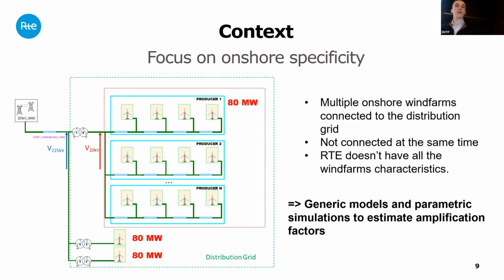Let's see the specific onshore wind farm topology when producers are connected to the distribution grid. Here you have the transmission grid with the long 225 kV cable, the transformer, and the distribution network, composed of several different producers connected to this distribution grid. The main challenge is that they are not connected at the same time.